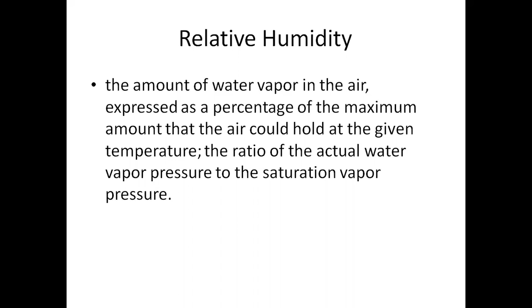But relative humidity is the amount of water vapor in the air expressed as a percentage of the maximum amount the air could hold at a given temperature. The ratio of the actual water vapor pressure to the saturation vapor pressure. So saying all that can really be described right here. So here is relative humidity, and notice at 10 degrees Celsius, that water vapor there is 100% humidity, but we know that a warmer gas can hold more humidity or more water vapor. So if we double that to 20 degrees, notice that 100% humidity drops to only 50% because there's more water vapor carrying capacity in warmer gas. And let's say that we triple that from 10, now we go to 30, then it almost drops in a similar ratio down to 28% relative humidity, because again, that warmer gas can hold more humidity.